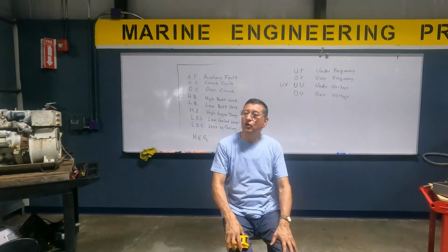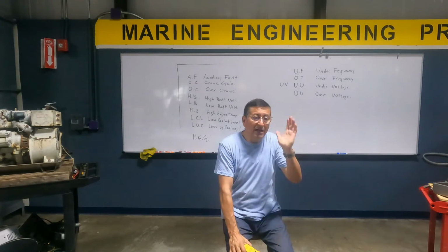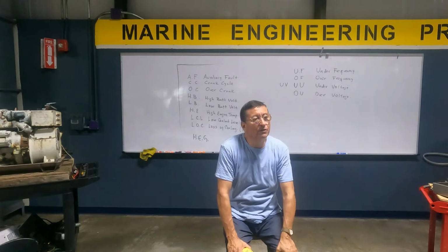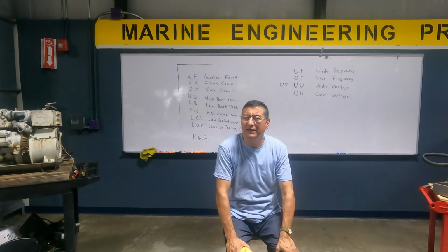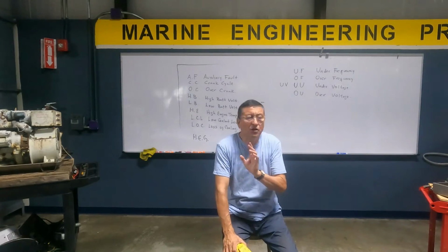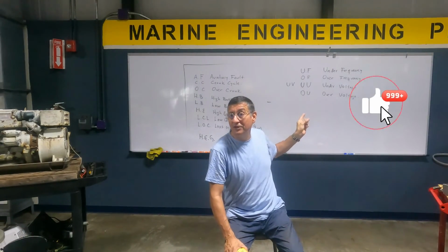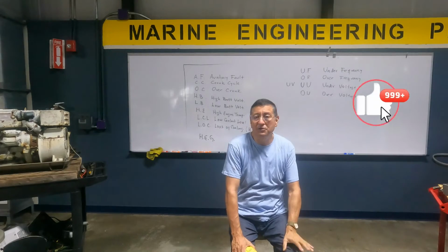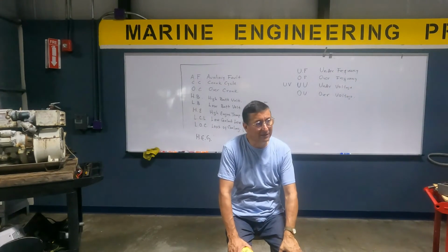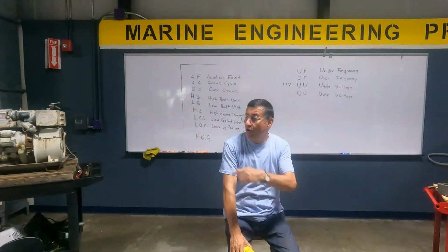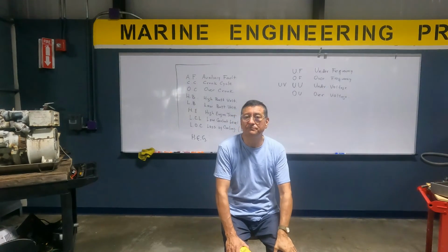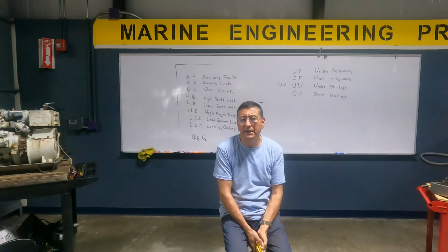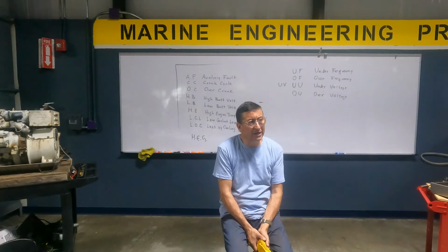Those are the most common codes. I don't know any other additional ones. It's not complicated. The electrical codes are high frequency, low frequency, high voltage, low voltage. That's it. And you know the process to calibrate and solve it. The other ones are mechanical problems. This is typically how to test, how to check a generator.